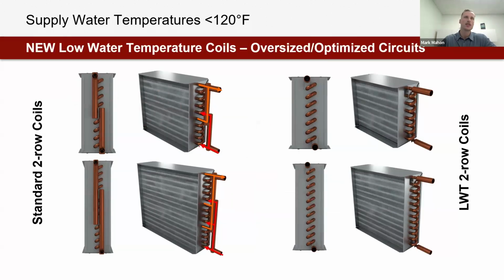And I'll draw a little bit on here too. What I want to note is we have water that's kind of shuffling through all the tubes and then going out the return here. And so when we have a 2-circuit coil like we'd see on the top of the screen, it is almost like two little heat exchangers within one housing and casing. And when we see a 3-circuit coil on the bottom, it's almost like 3 little heat exchangers within one terminal casing.